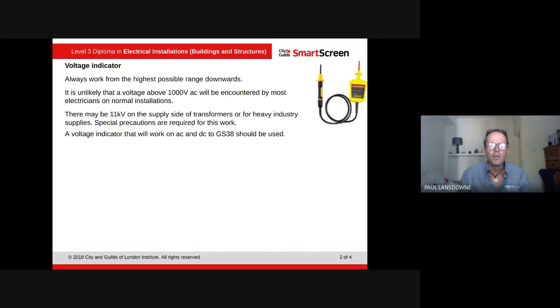A voltage indicator that will work on AC and DC to GS38 should be used — we've looked at GS38 in the previous unit, which covers finger guards and the tips. Always make sure an approved voltage indicator has a range above the supply voltage, as we've said.